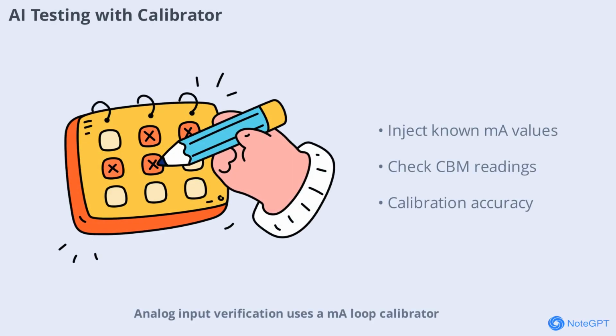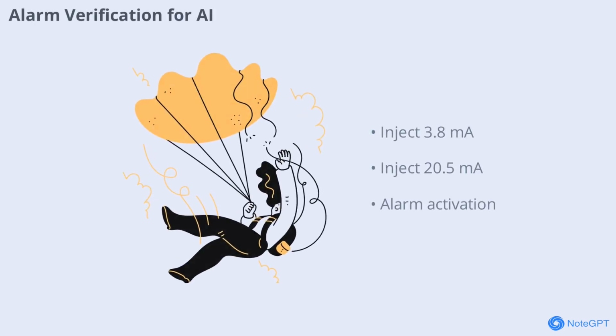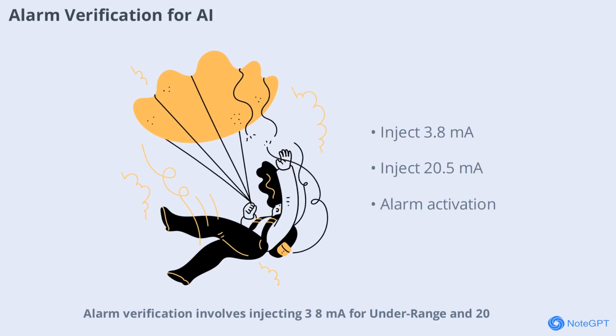Analog input verification uses a mA loop calibrator to inject known values into the AI module terminals. The control room engineer checks that both the raw and scaled values in CBM match the injected current. This process ensures that analog inputs are calibrated and functioning correctly. Alarm verification involves injecting 3.8 mA for underrange and 20.5 mA for overrange alarms.